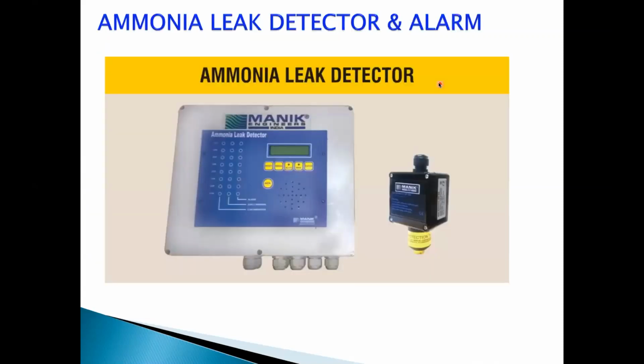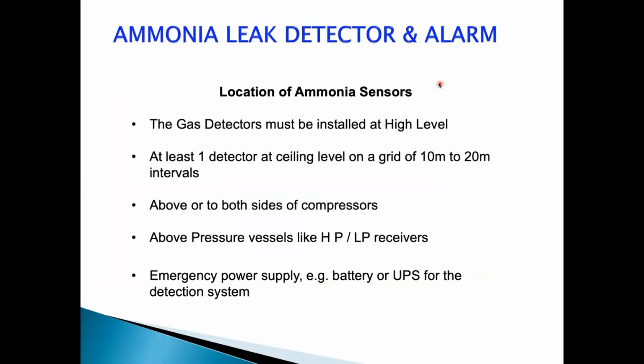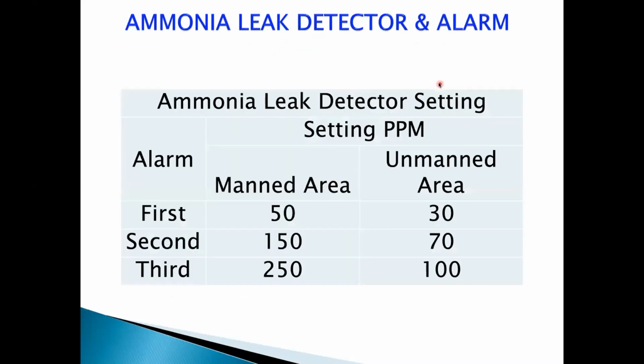The most important safety part is the ammonia detection system. We need to install sensors so that ammonia leak detection can be done and alarms can be operated. As I told you, ammonia gas is lighter than air, so whenever it leaks, it goes up. So you install sensors at a higher level, and maybe on your pressure vessels, valve stations, compressors, so that in case of ammonia leaks, the gas will go up, the sensor will sense it and give a signal. You should have a battery backup or UPS system, so even if your power supply fails, the ammonia leak detection system works continuously.